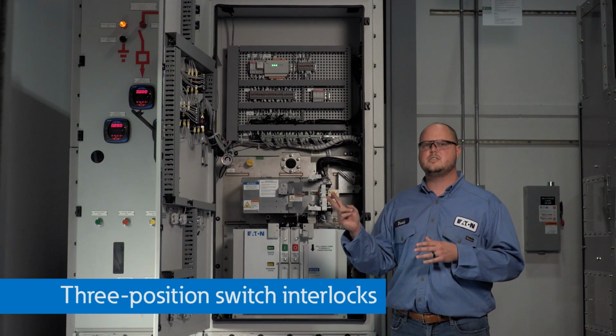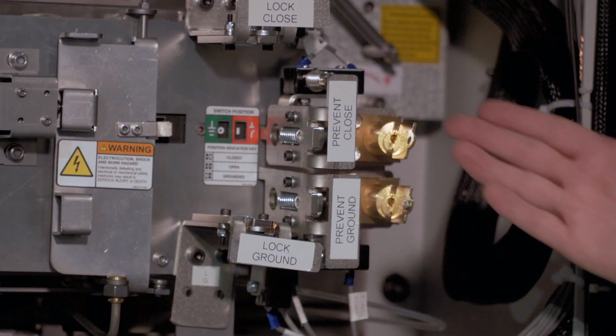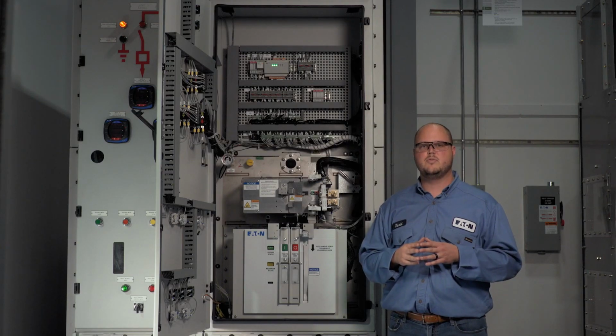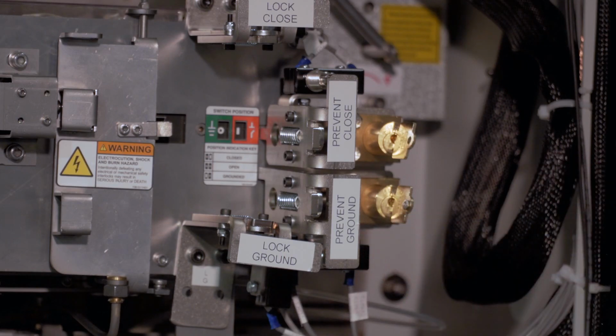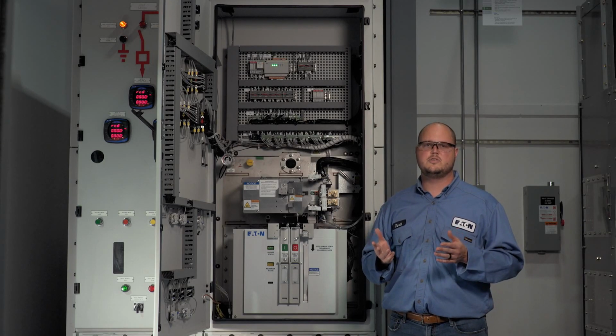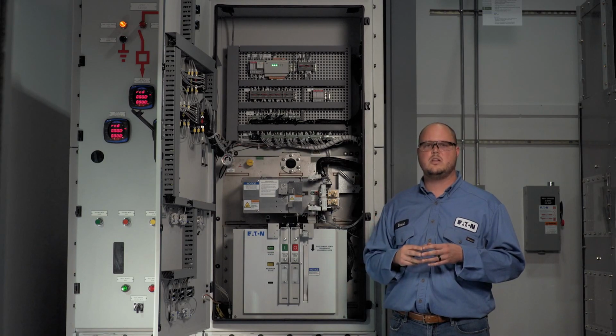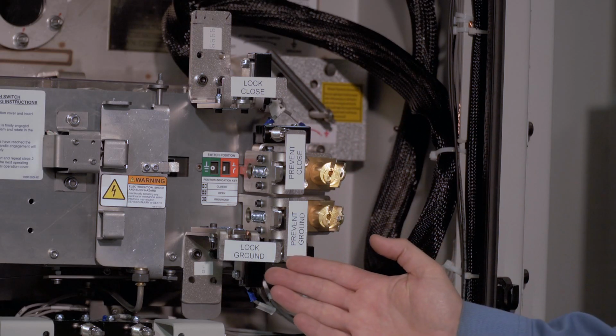And the Power Xpert XGIS gas-insulated switchgear offers some additional interlocks not common in air-insulated switchgear. These 3-position switch interlocks are used for controlling and or limiting switchgear operation during normal use or during scheduled maintenance events. 2 standard features on all xgis switchgear are the switch prevent close lock and the switch prevent ground lock. xgis switchgear also offers 2 optional locks, the switch lock close lock and the switch lock ground lock.